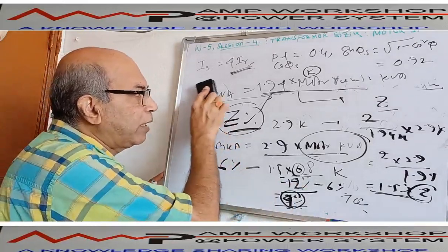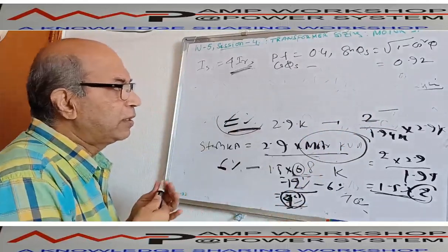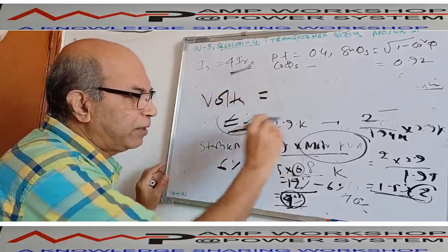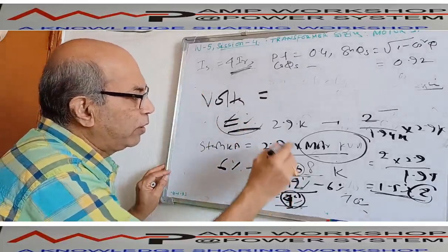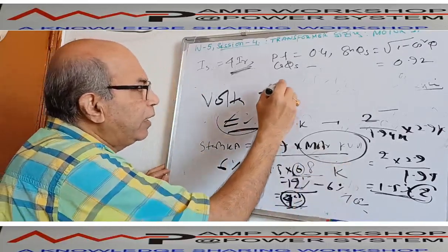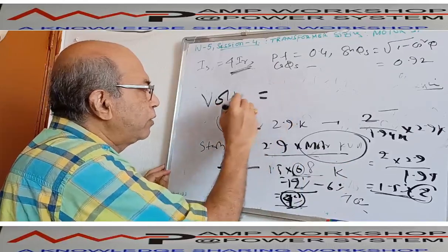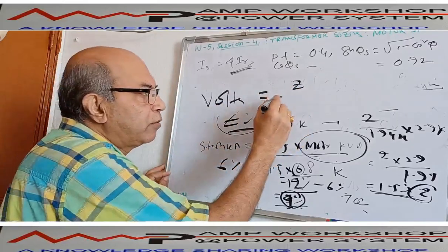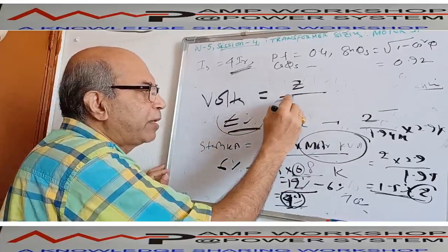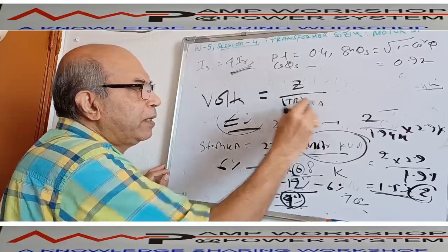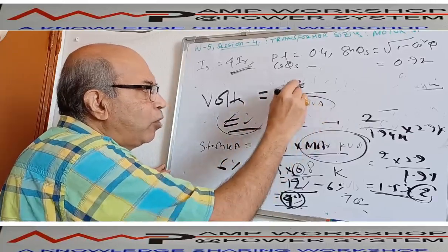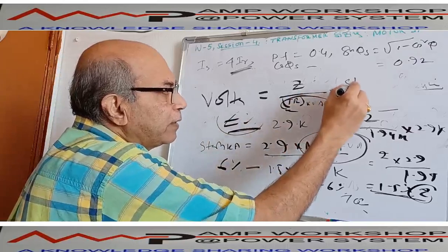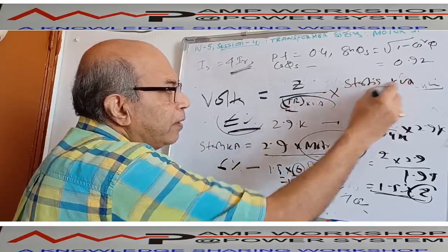This voltage drop we can also calculate another way. This voltage drop calculation is very simple. You can see from this point we can calculate Z percent voltage drop for this transformer rating. That means voltage drop equals Z percent impedance. So Z percent voltage drop is for the running transformer KVA, the transformer rated KVA. So for one transformer rated KVA, the voltage drop is Z. So for the starting KVA, you can write down the starting KVA, this amount.